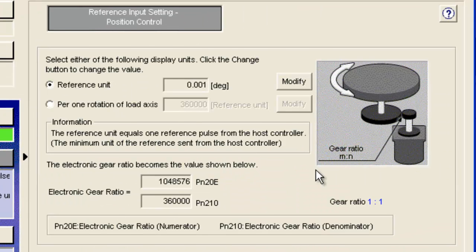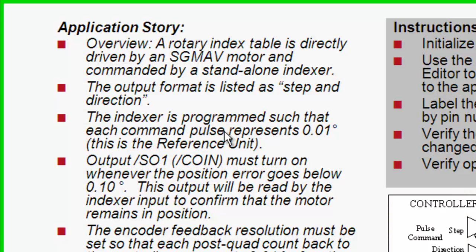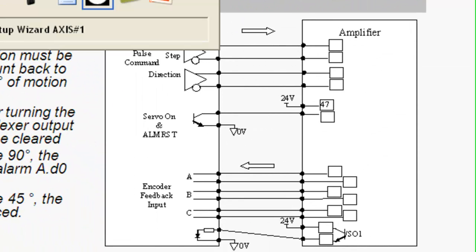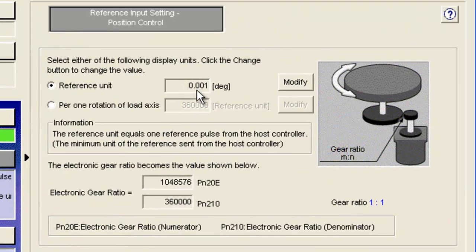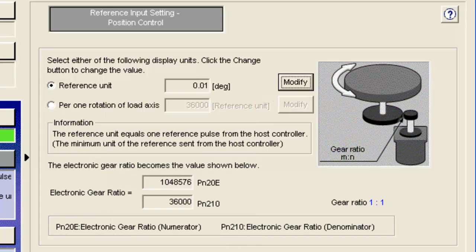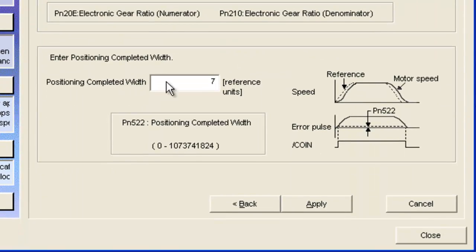Next here's the reference unit, and this refers to the distance that the machine should move when one pulse comes from the controller. We call that the reference unit, and I want to set that to 0.01 degrees. So see here that's been set to 0.001 degrees by default. I'm going to modify and just knock off a zero here.